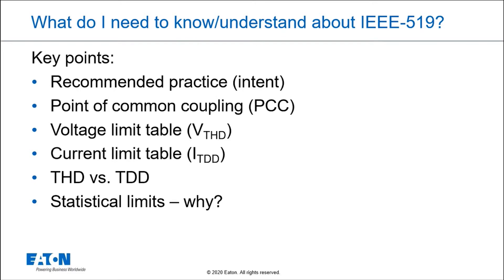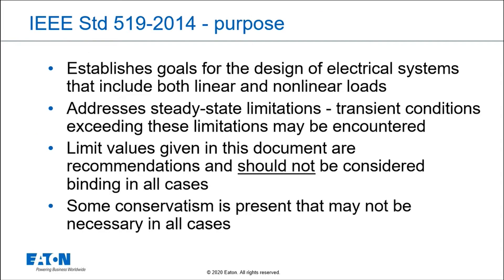It's important to understand the point-of-common coupling, the voltage limit table, the current limit table, THD versus TDD, and why we have statistical limits. The 2014 standard replaced the 1992 standard, which hadn't been changed in a long time. There were minimal changes except the document went way down in size and got very focused. The important things are that it establishes the goals for the design of electrical systems that includes both linear and nonlinear loads, or harmonic-producing loads.